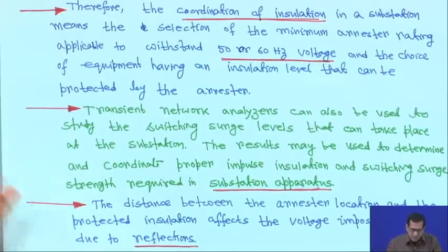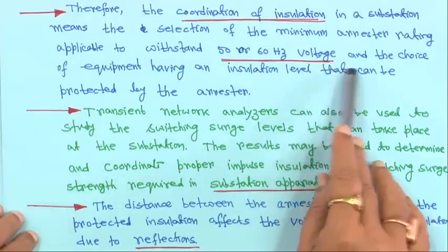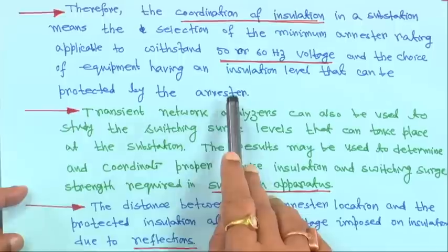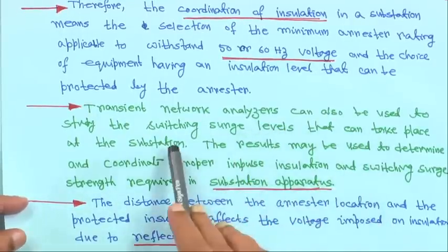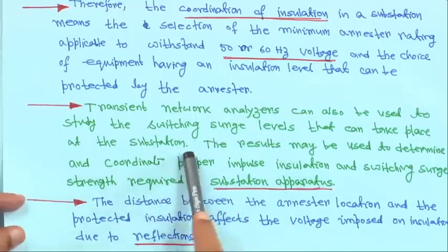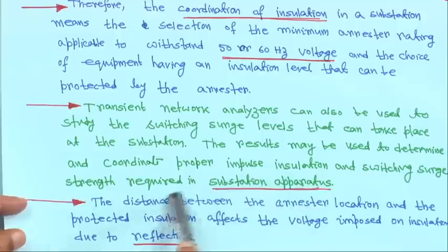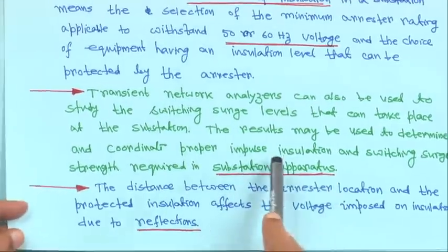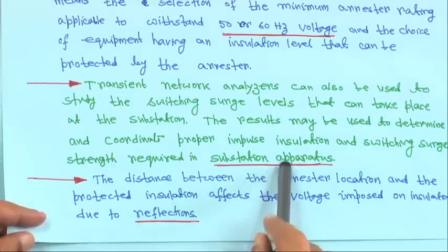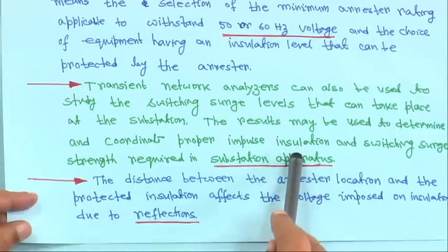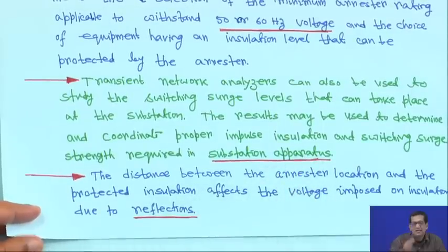The coordination of insulation in a substation means the selection of the minimum arrestor rating applicable to withstand 50 or 60 Hz voltage, and the choice of equipment with an insulation level that can be protected by the arrestor. A transient network analyzer can also be used to study the switching surge levels that can take place at the substation, helping determine proper impulse insulation and switching surge strength.